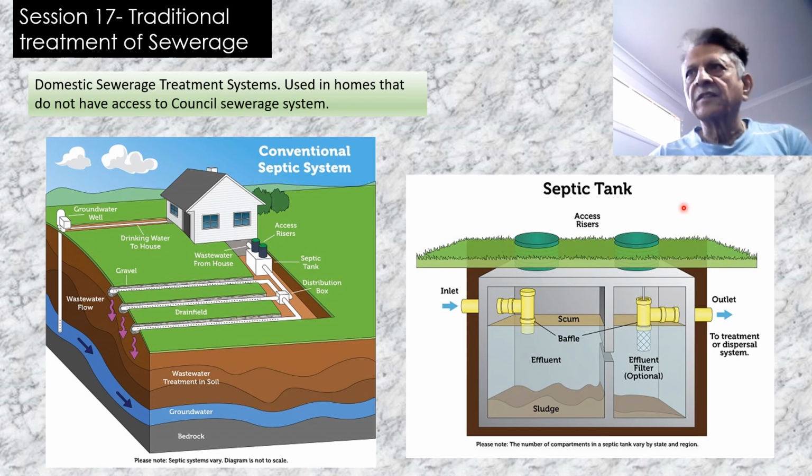So this filter will ensure that it is clear water that goes in. Over a period of time, the sludge is collected and it will start increasing until it will interfere with the treatment systems, when you will have to stop the system, open up the access and pump out the sludge effluent and restart the system.